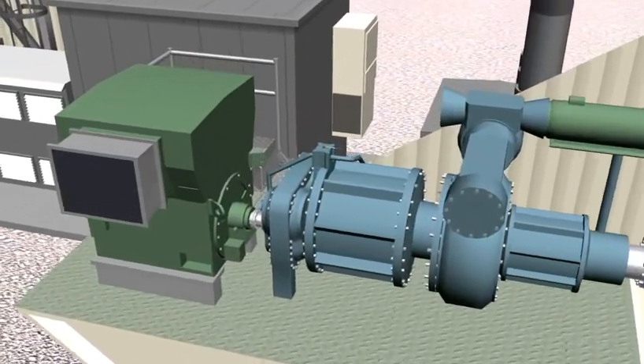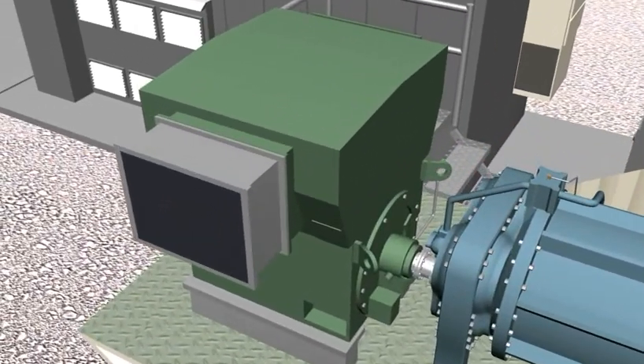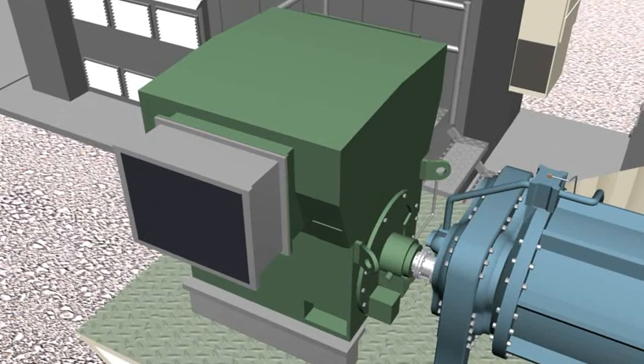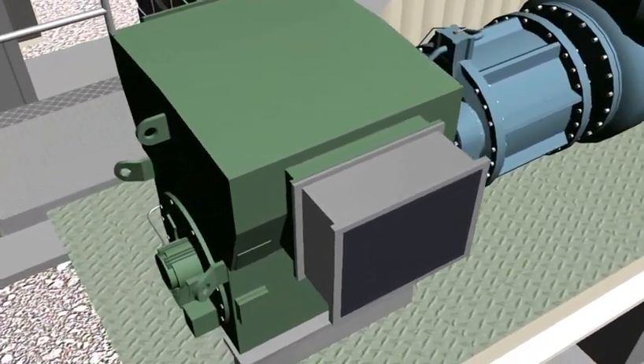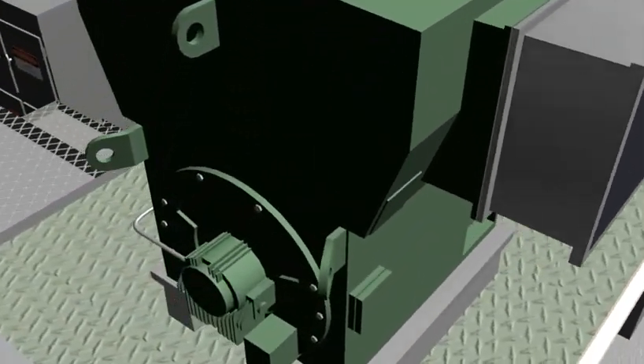The 4,160 volt AC starting motor is used to initially accelerate the combustion turbine up through ignition and roll up until a self-sustaining speed is reached. At this point the starting motor is disengaged.